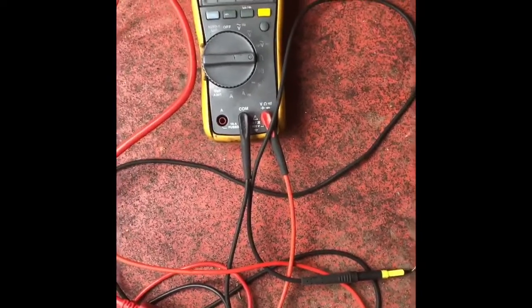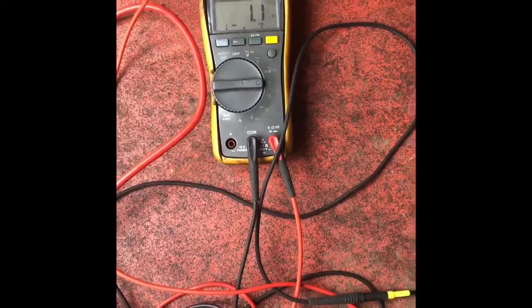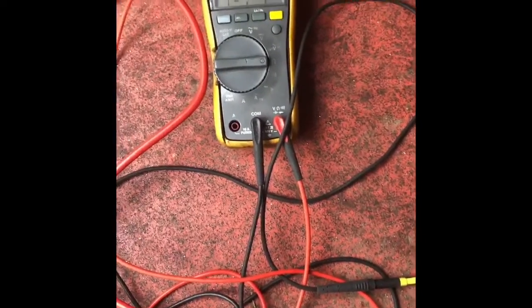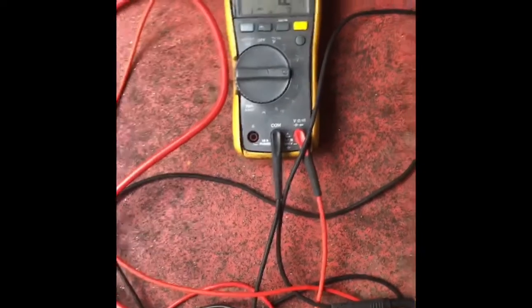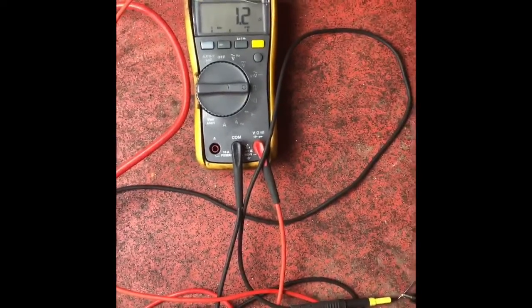But the load probe, obviously, if I load up the cable and press the button, I can see the voltage drop like a stone. Now obviously this MAN has got a problem with that plug there, we're in agreement with that. I power up the cable, I'll have power here, but on the other side I don't actually have power, because that pin there will not make contact with the pins through here. So effectively you have what we call an open circuit.